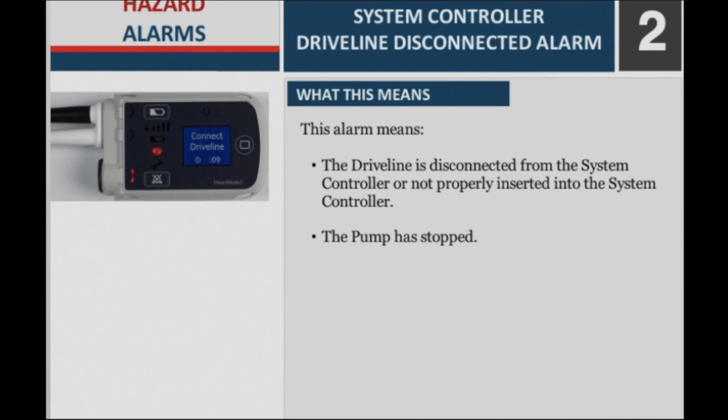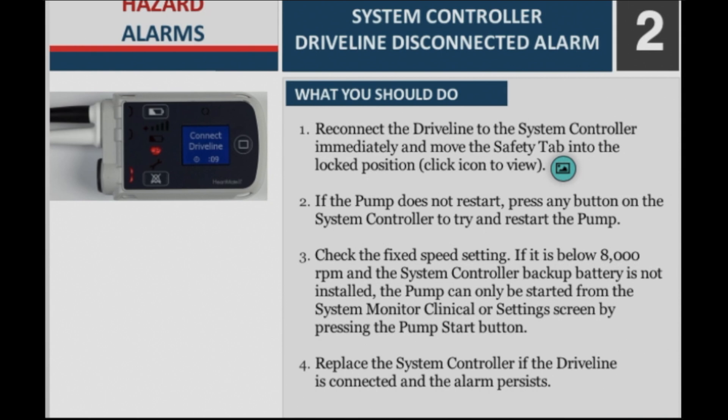What this means: The driveline is disconnected from the system controller or not properly inserted into the system controller. The pump has stopped. What you should do: Step 1 — Reconnect the driveline to the system controller immediately and move the safety tab into the locked position.